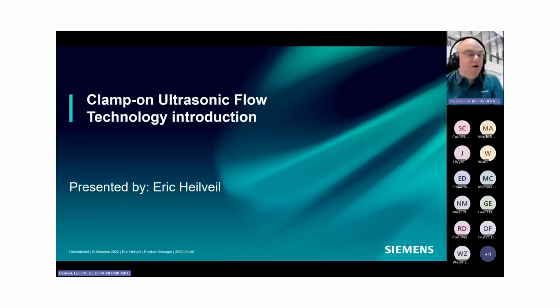One thing to remember before I even start off is that at its heart, clamp-on ultrasonic is a non-intrusive flow measurement system. So in short, clamp-on ultrasonic goes on the outside of the pipe, non-intrusive. You can install it while you're still flowing. You don't have to open the pipe, cut the pipe, stop the flow upstream or downstream or any of that. So that's great. How does this whole thing work?